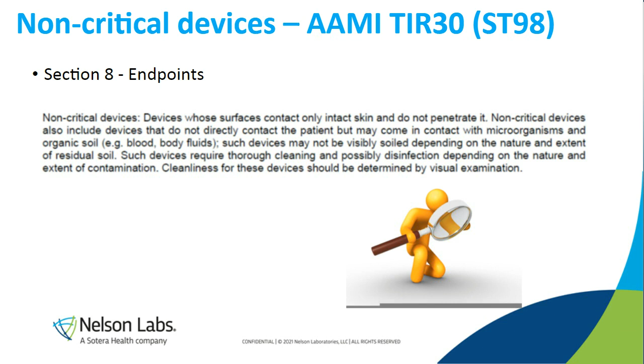Along those lines, non-critical devices: a new segment of ISO 17664-2 was published this year, and this document only focuses on non-critical devices. In this document, it says in 6.2.1, in the last sentence, disinfection may be carried out concurrently with cleaning of the medical device. So it does allow certain products to be a combined process. That's what we would call a combined validation, where cleaning and disinfection can be performed in one step.